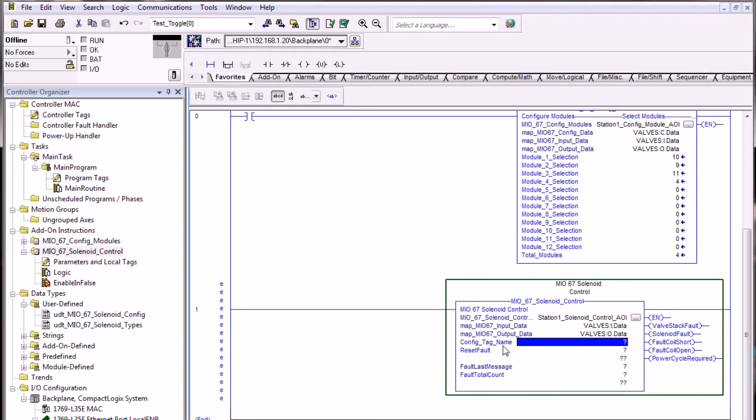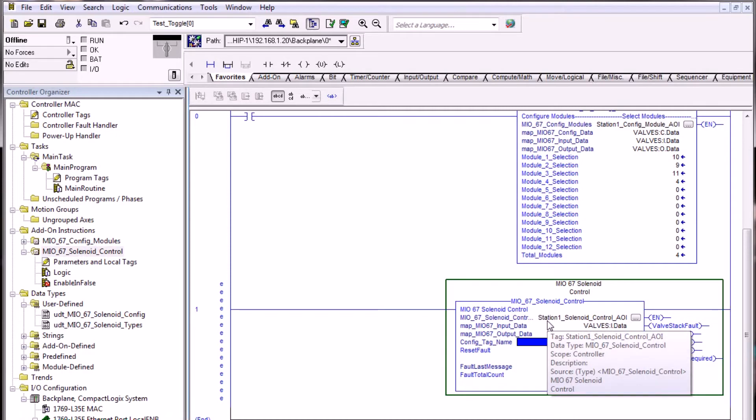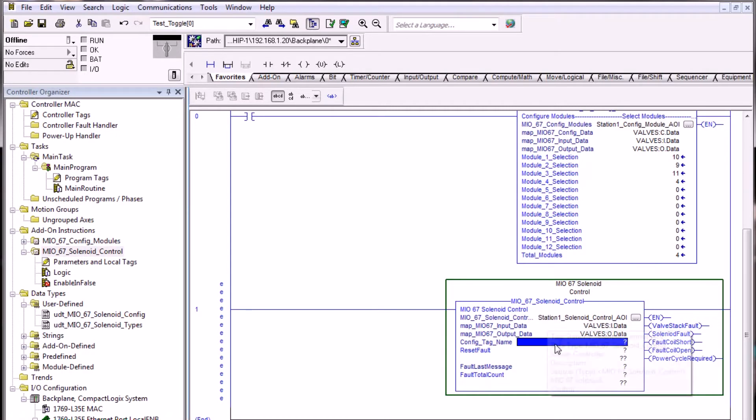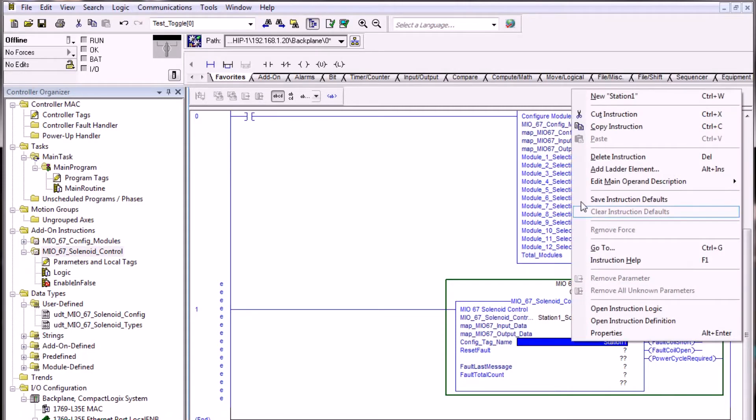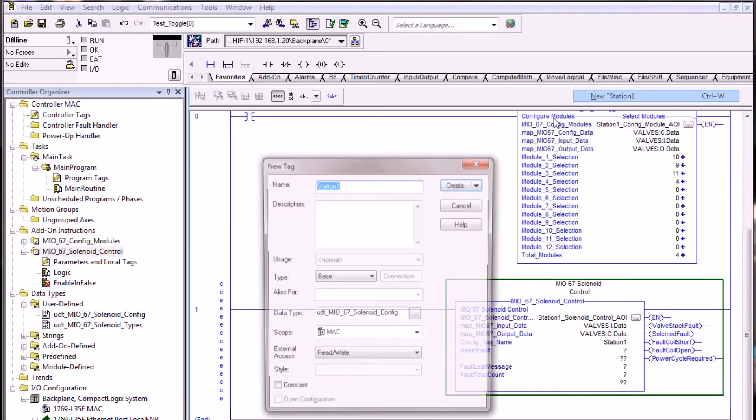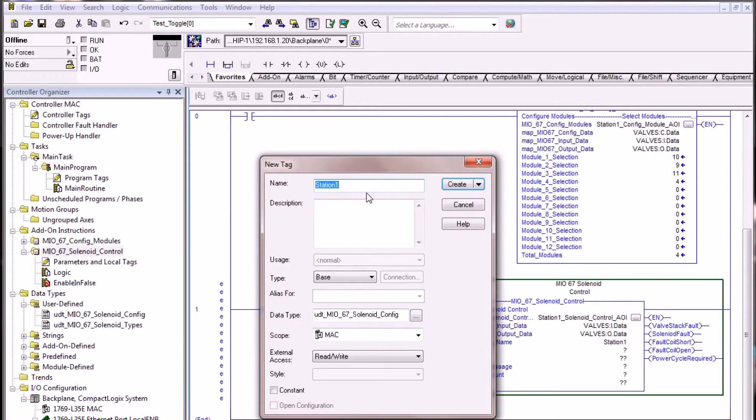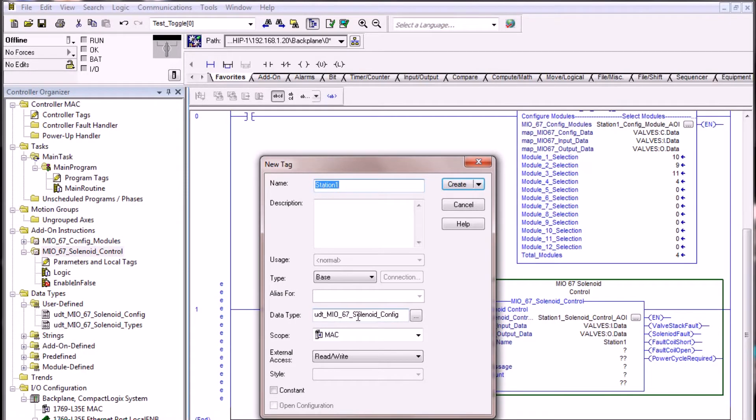The config tag name is fairly important. You'll want to use a short name here as this is how we're going to be referencing solenoids in our project. Because we're using the concept of this is station 1, it might be a good idea to give the config tag name that particular tag name as well for station 1. We'll go ahead and right click on this to create a new station 1 tag, and this creates it as the UDT of MIO 67 solenoid config.